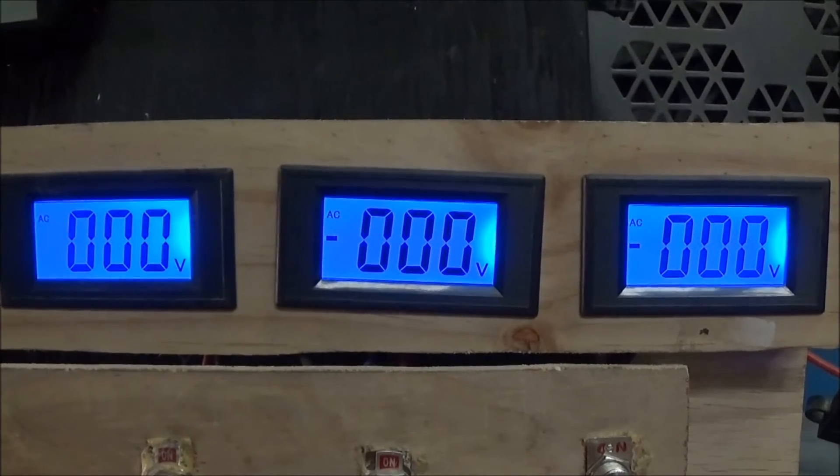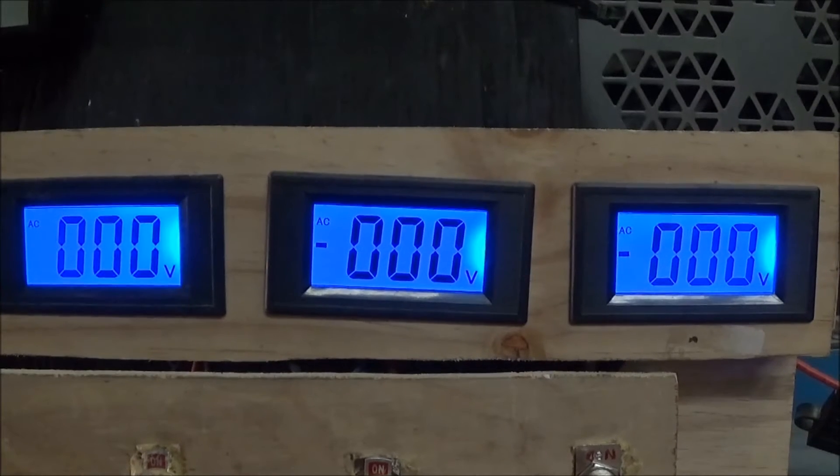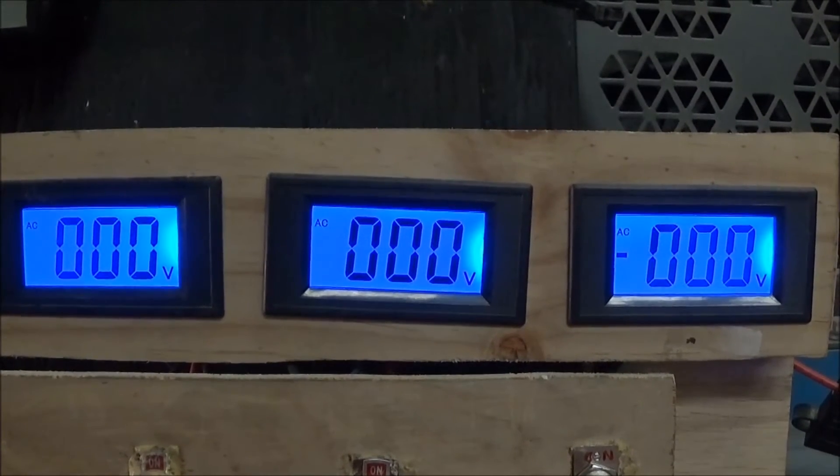This bank of AC voltmeters will measure the three outputs simultaneously. We'll be able to check the outputs and see if there's any kind of phase imbalance. All right, let's spin it up.